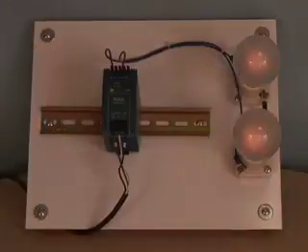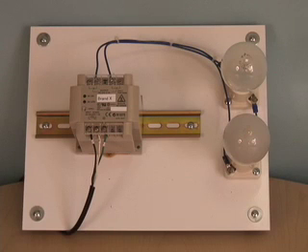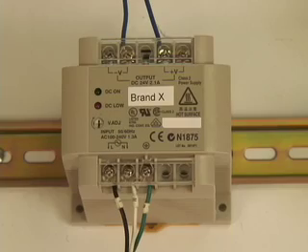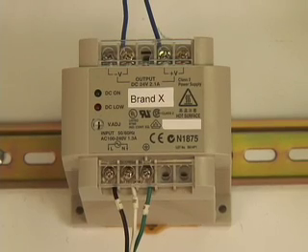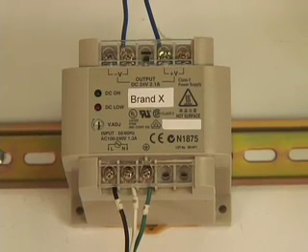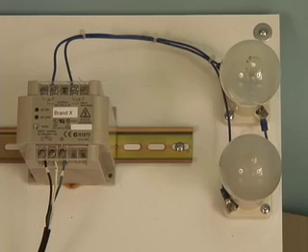If we energize the hiccup mode power supply, you will see that the lights do not turn on, which would make it seem that one of the light bulbs is burned out or there is a problem with the wiring, but this is not the case. If we look closely at the LEDs, you will see that the DC low light is flashing, indicating that the load is too much for the power supply to start.